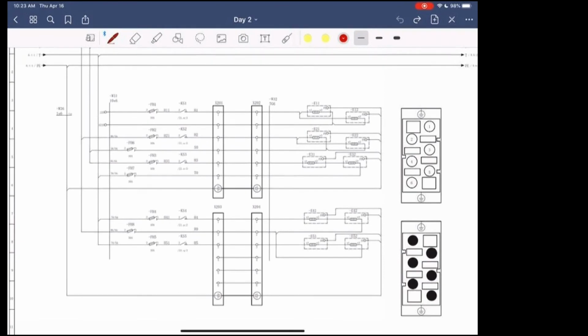That being kept in mind, one thing you have to be cautious of is this heater band, because it has a grounding system on it. If the heater band would ever go to ground, which is this one, I'm sorry, it would also complete the circuit, even if the power was off going to this heater band, because it's a complete circuit. The only reason it would stop is if this K1, if the grounding was caused before the power, not the return. If it was caused by the return, then obviously you'd have a complete circuit.